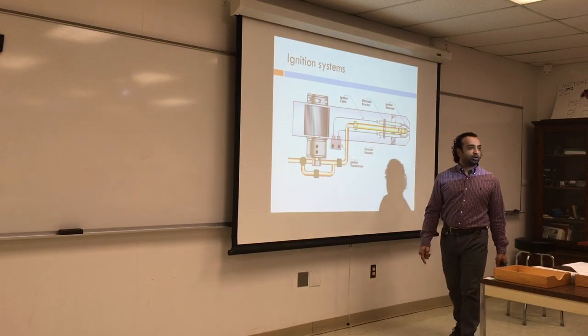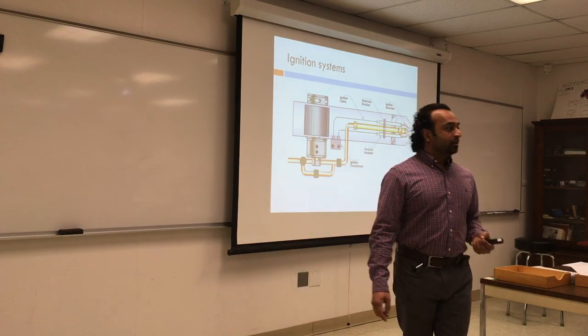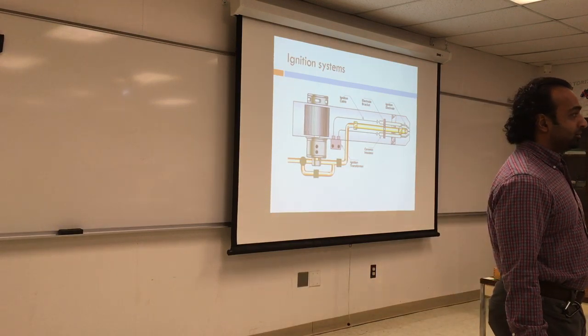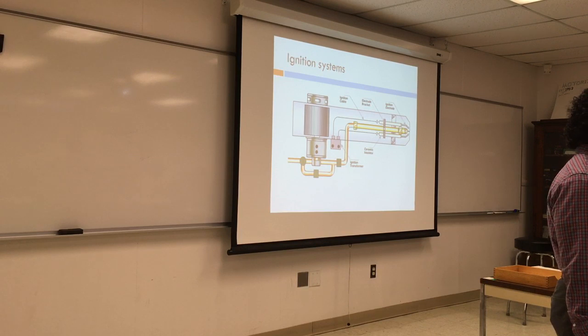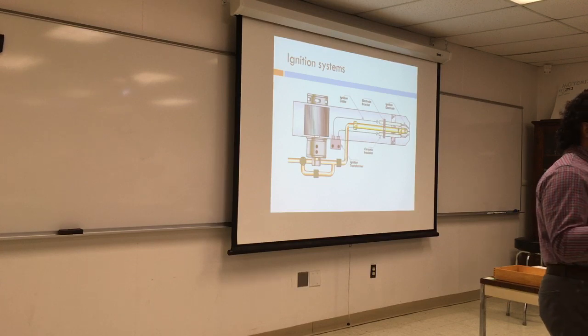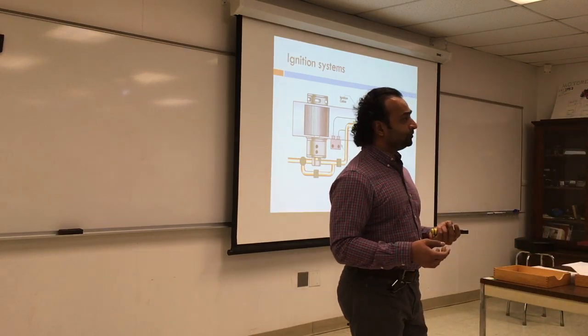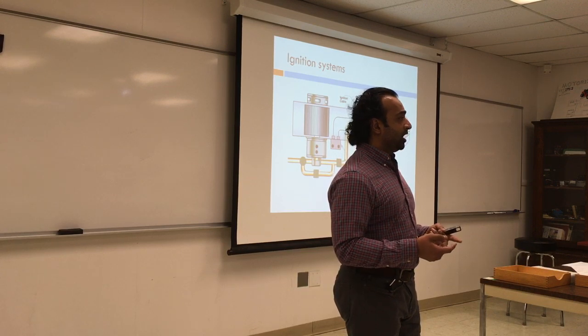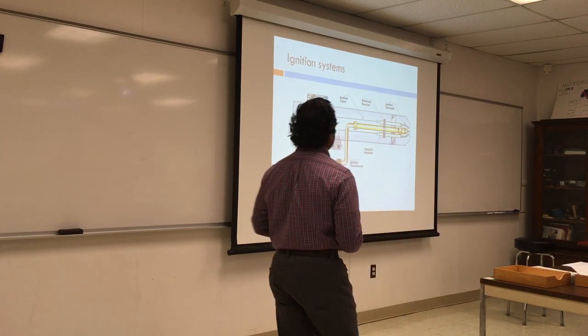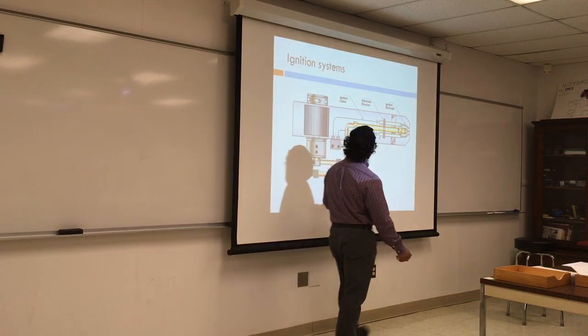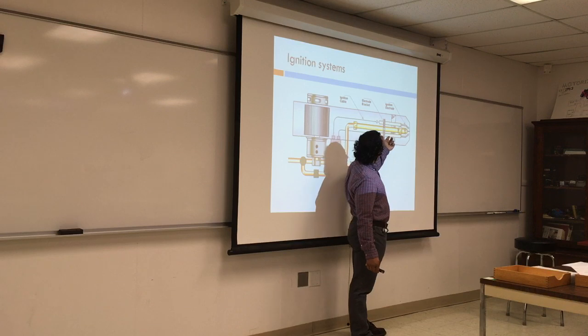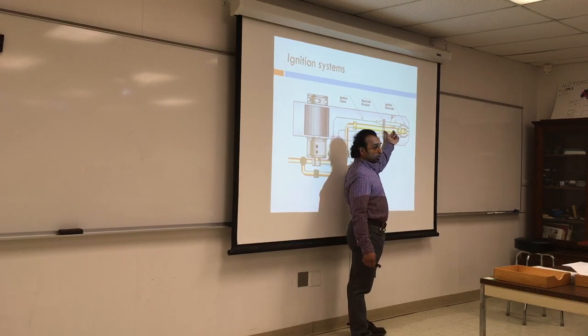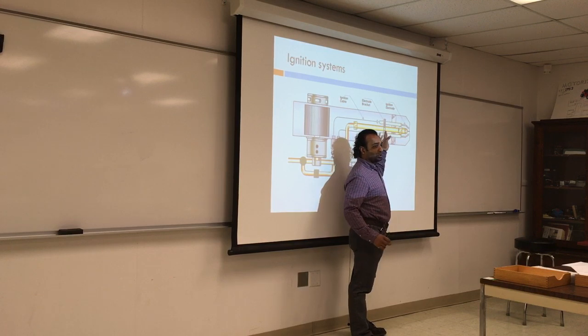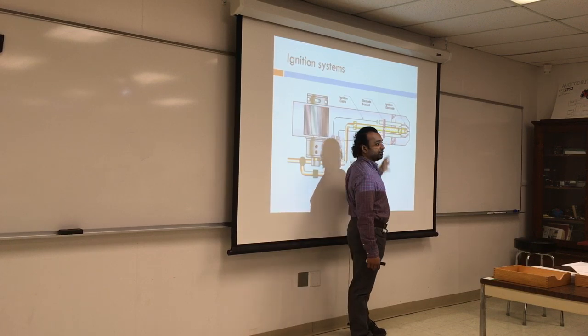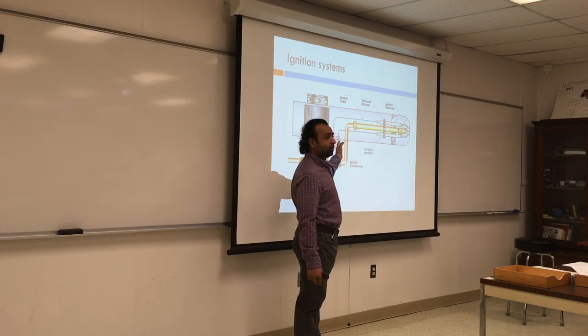It's also very important to have what is the code now, which is called interrupted ignition. What does interrupted ignition mean? It's not continuous. It will stay until we prove the flame, then it will cut out. Older models have something called intermittent ignition, which means constant. The whole time the ignition is constant, which was very wasteful. The electrodes are held by a ceramic holder and a spacer that keep them in place. So make sure when you put it in there, it's in place and the center is not touching anything. Be very careful touching the casing while the electrodes are on.